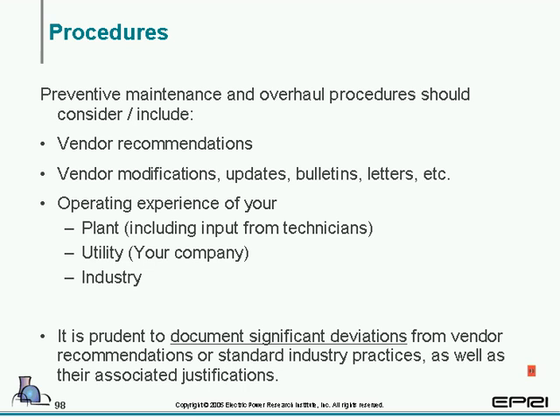Moving on to procedures. Preventative maintenance and overhaul practices should consider or include vendor recommendations, and a lot of times, again, those are in the vendor manuals that you get originally. But in addition to that, procedures need to be updated through vendor updates, bulletins, letters, or any other modifications that the vendor may have come out on your circuit breaker. And in addition to that, you should also include your own operating experience from your plant via input from your own technicians. These are the guys that work on your breakers, PM the breakers, so they have the most intimate knowledge of your breakers.